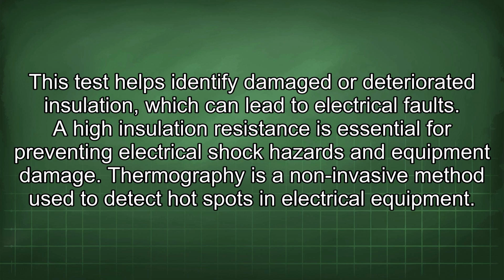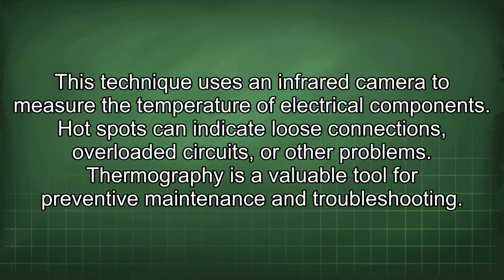Thermography is a non-invasive method used to detect hot spots in electrical equipment. This technique uses an infrared camera to measure the temperature of electrical components. Hot spots can indicate loose connections, overloaded circuits, or other problems. Thermography is a valuable tool for preventive maintenance and troubleshooting.